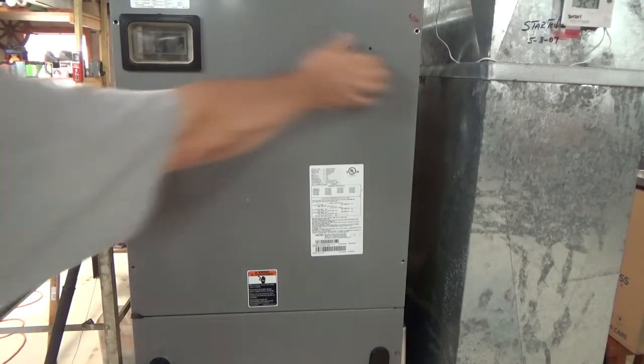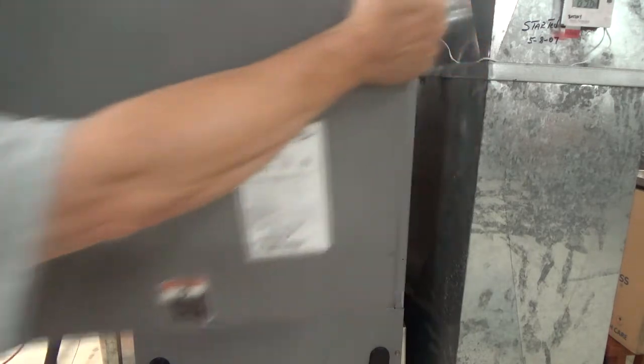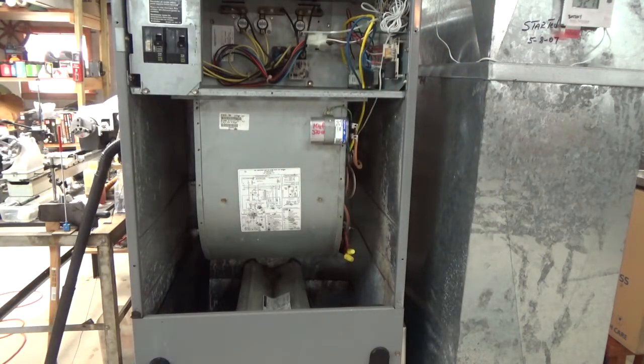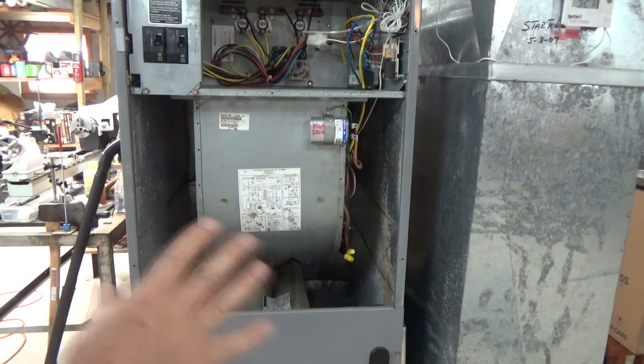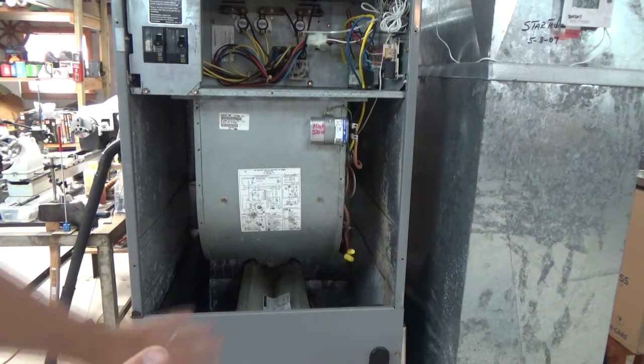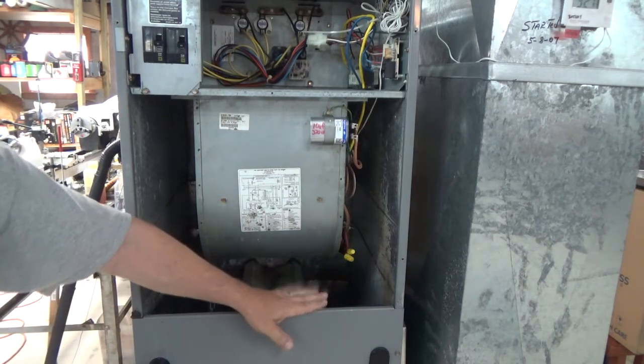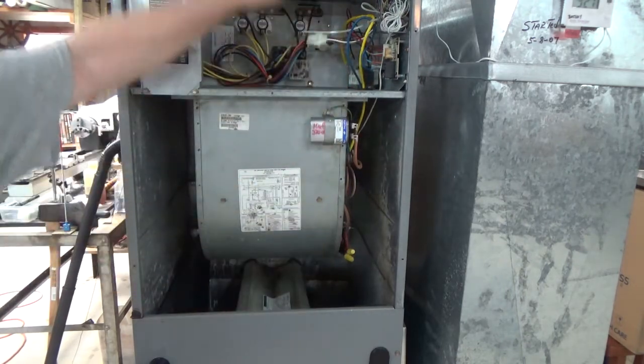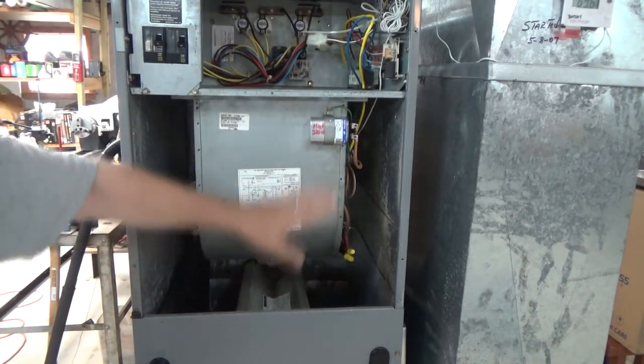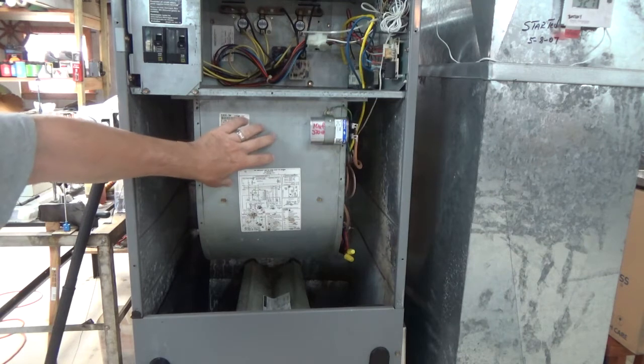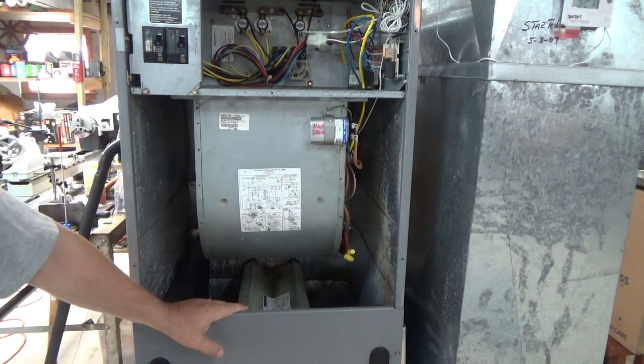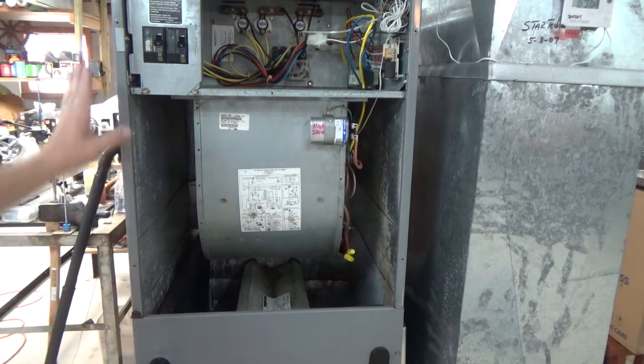With the power off, you can take the screws out and take the panel off, which will reveal the upper side of the air handling unit. A lot of times these are laid on their side, but still the lower unit won't come off - the top panel has to come off first. So if it's laying on its side, the motor panel will come off before the coil panel will come off.